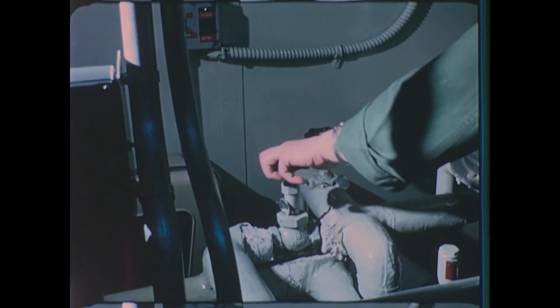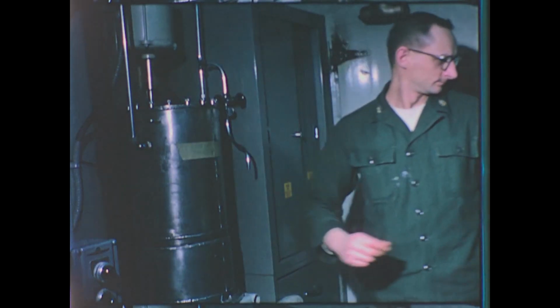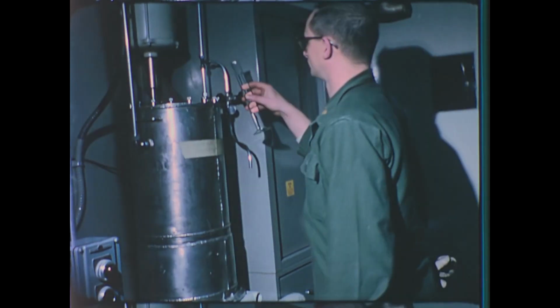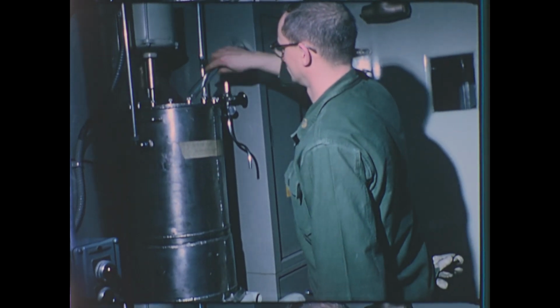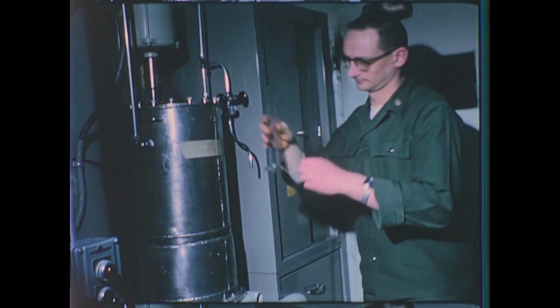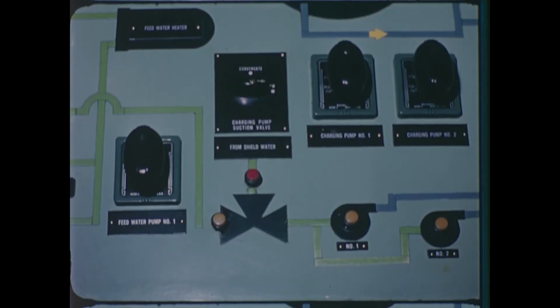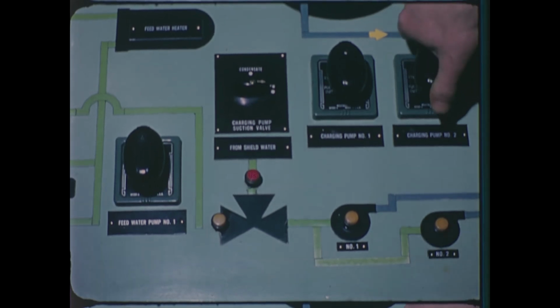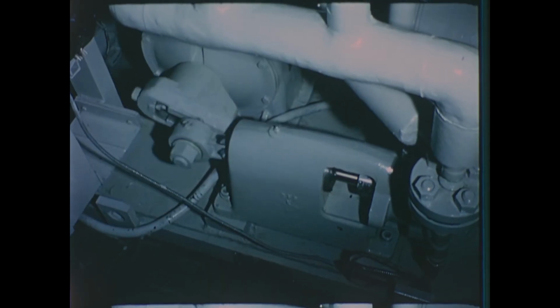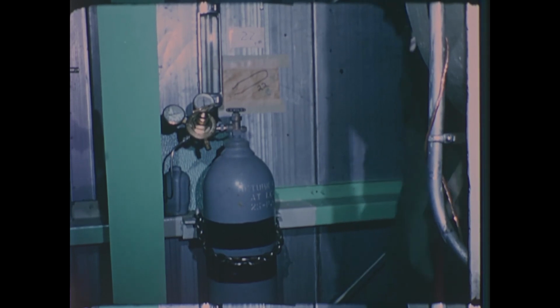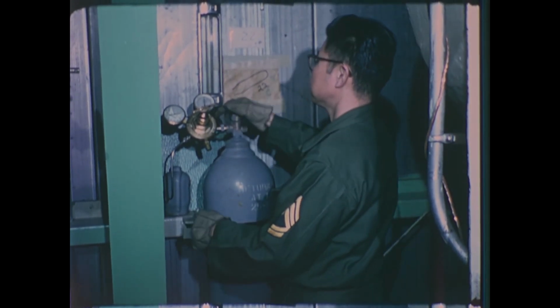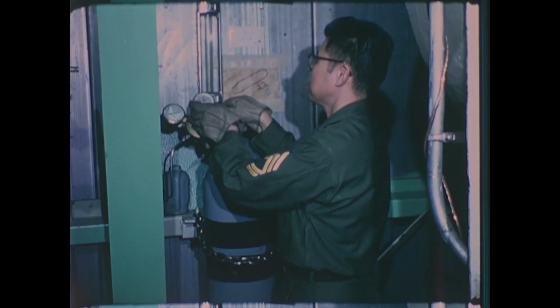During chemical addition, with the demineralizer isolation valve closed to keep chemicals out of the demineralizer, the operator lines up suction to the chemical addition tank. He adds hydrazine before reactor startup to scavenge oxygen from the system. System temperature of less than 190 degrees is maintained by the decay heat pump. A pump control switch located at the console puts the coolant charging pump in operation. Nitrogen pressure in the expansion tank is maintained between 5 and 15 psig. Regulator is located at the HTA package.